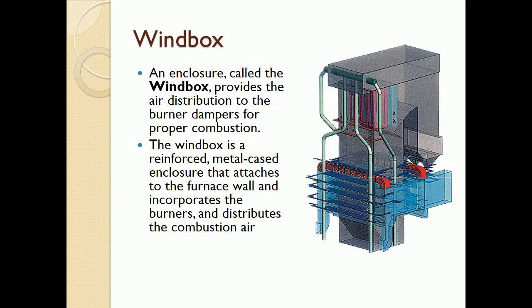The windbox is an enclosure that provides the air distribution to the burner dampers for proper combustion. The windbox is a reinforced, metal-cased enclosure that attaches to the furnace wall, incorporates the burners, and distributes the combustion air. The air coming from the air heater pressurizes the windbox.